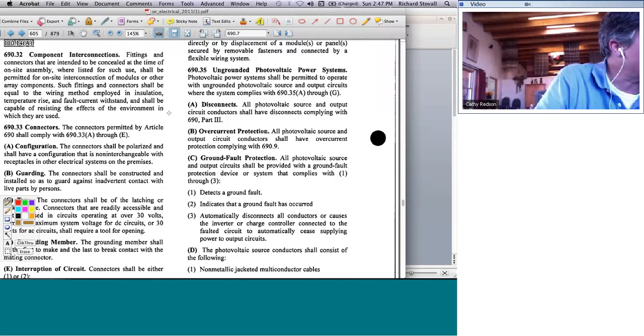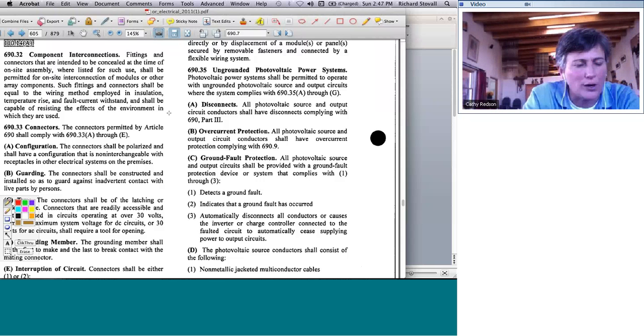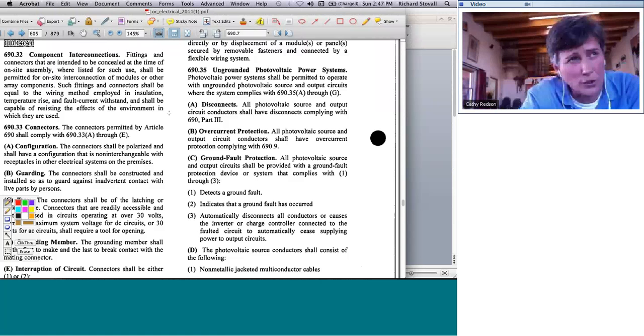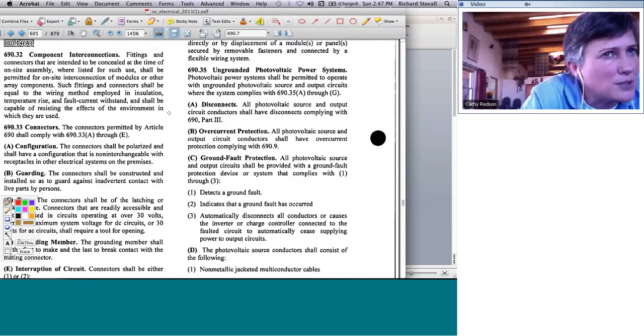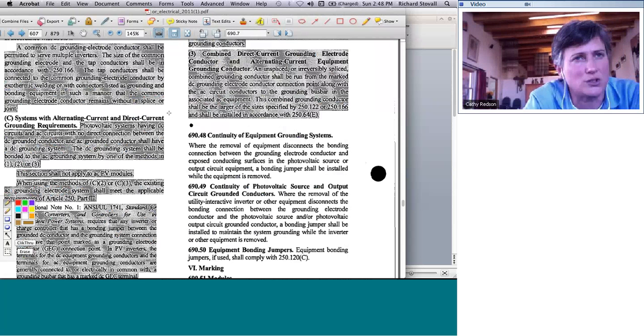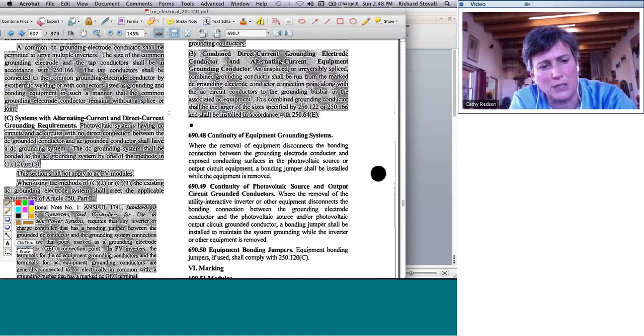In solar, what that now means is somebody that has received training with respect to safety, as we saw there in Article 100. So if someone's working with solar equipment and they haven't received training specifically in working safely with photovoltaics, then technically they do not qualify, even if they're a licensed electrician, to work on solar. This is something that in an issue last summer in 2011 of Solar Pro, several people were commenting on and saying that this was unprecedented, that you needed special training relative to the equipment, because generally, journeymen or master electricians are licensed in most states to do any kind of electrical work. And then here they're saying that they must be installed by people that have received that actual safety training in that type of equipment. So that's a big change and got pages and pages of comments during the review cycle for the 2011 code book release.